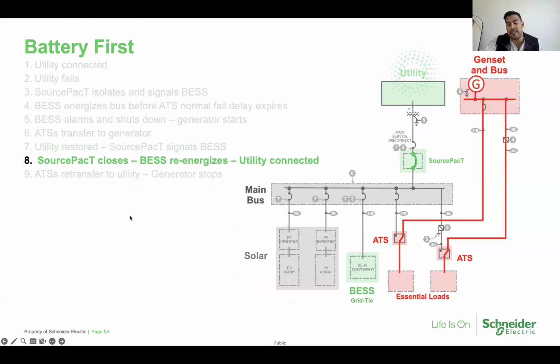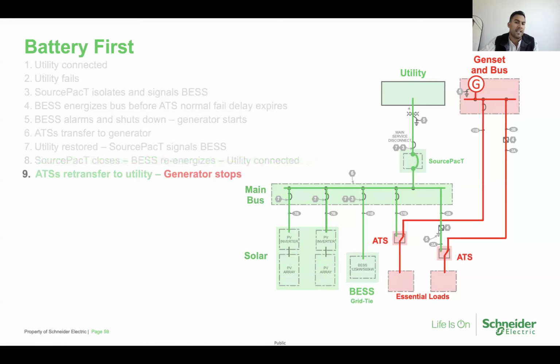At the same time, the ATSs are connected to source 2, so you have that isolation through the transfer switches. And again, the transfer switches, when they sense the utility has been restored, will retransfer back to utility in an open or closed transition, depending on what's specified. And then the ATS sends a generator stop signal to the gensets to cool down.